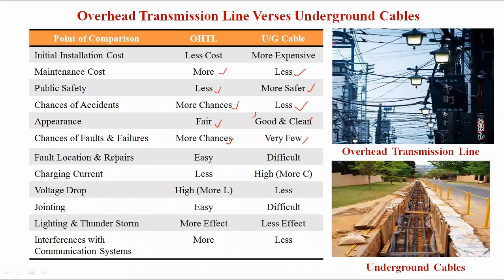Fault location — identification and rectification of fault is easy in overhead transmission lines because all parts and conductors are visible to the naked eye. But in underground cable, identifying where the fault has occurred is very difficult and rectification is also difficult. Effect of charging current: in overhead lines the charging current effect is less, but in underground cable it is more due to capacitance. The three parameters are resistance, inductance, and capacitance. Charging current IC = 2πFC × V_phase.